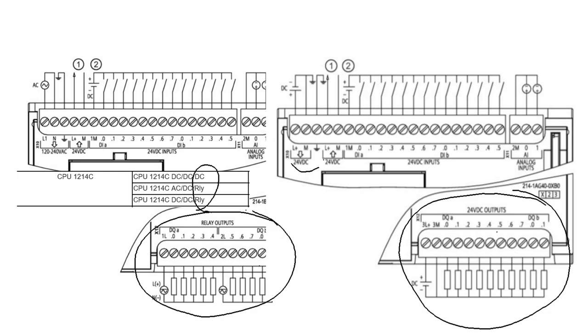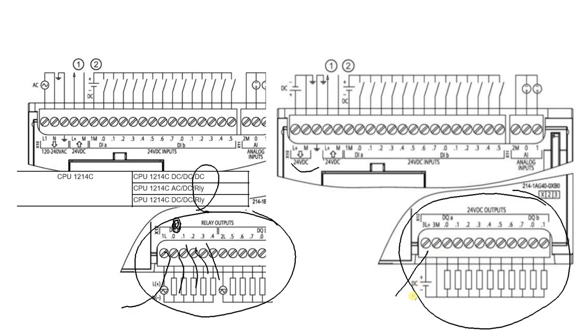So when you're talking relay, that's going to be power coming in and what's relayed out for each individual output once they are turned on by the PLC. Compared to this 24 volts, you put plus 24 and minus 24, and then you will reference from your output to your device back to minus on the output side.